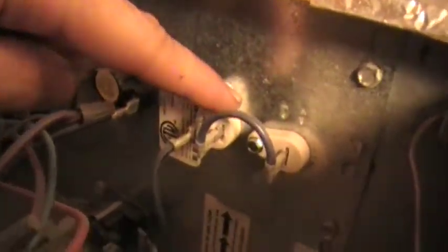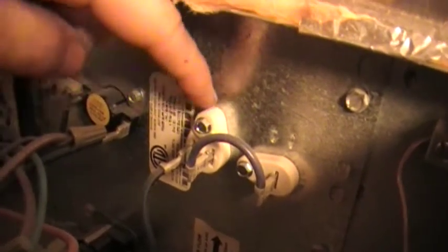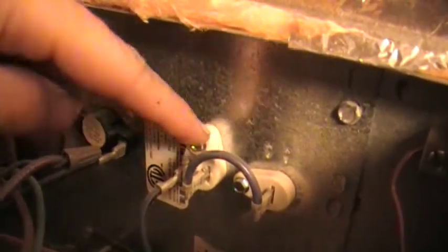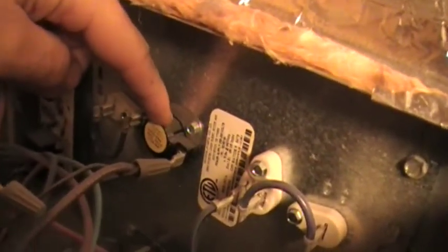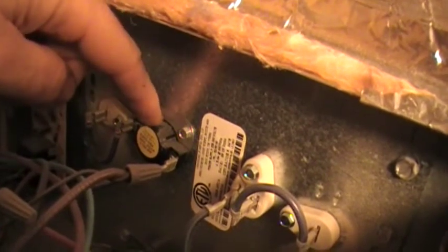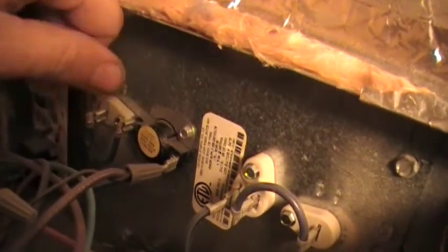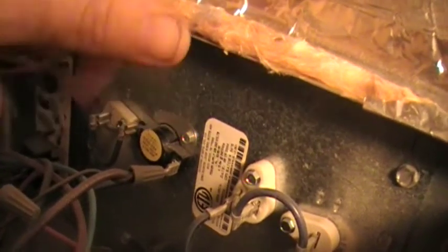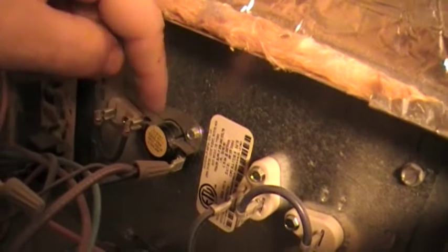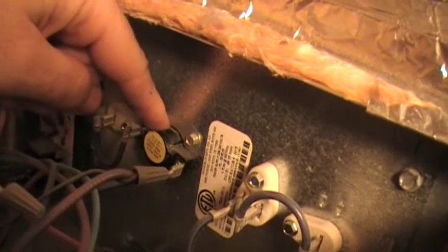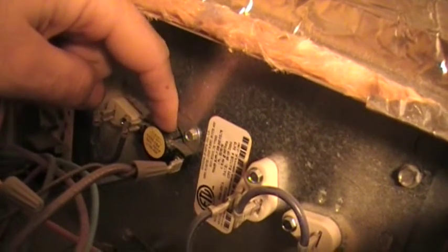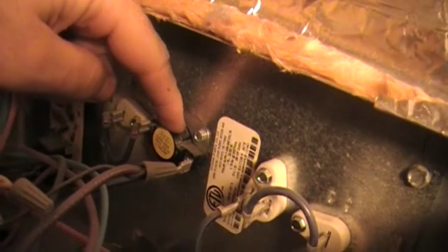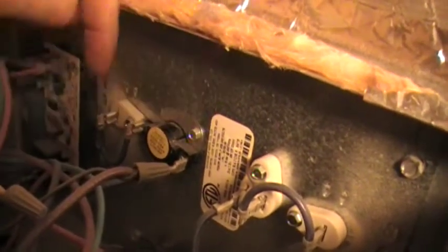Of course, all these right here are going to be your electric heating elements. It's going to be your emergency heat or strip heat. And you got some here and you got some over here too. And typically when you see a little thing like this right here, it's a type of bimetal thermal overload device. In other words, if you ain't got good airflow through the unit itself, then this is going to get too hot and it's going to open the circuit, turn off your heaters. That keeps you from having a fire and stuff like that. It's a safety device.